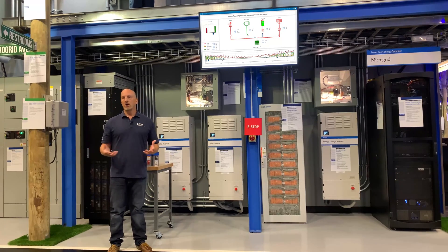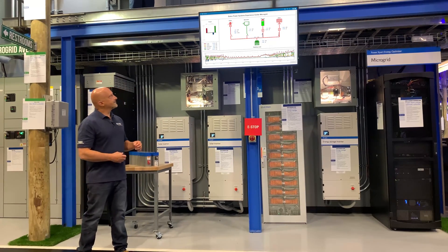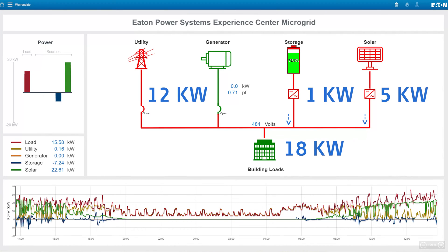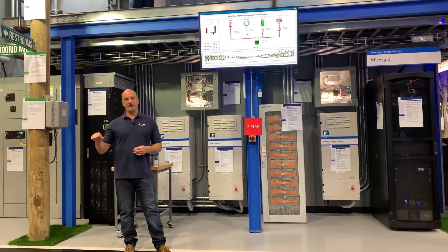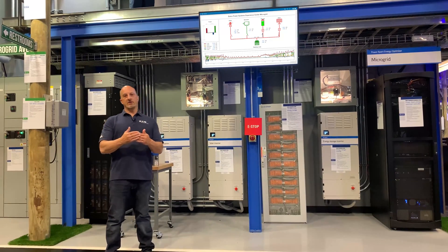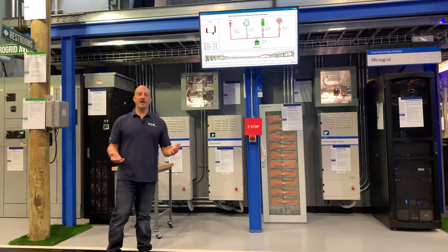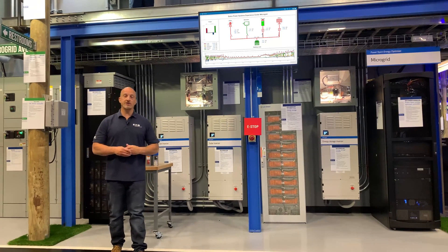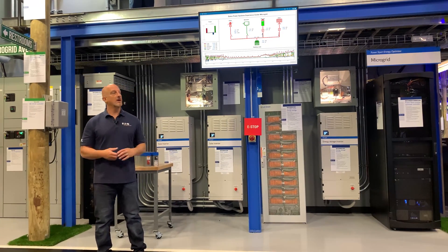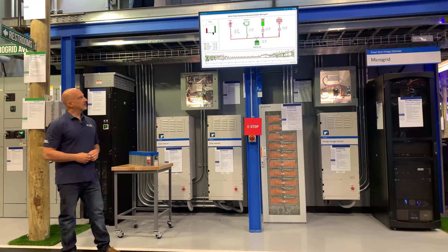Right now we have 18 kilowatts of power — 12 is coming from the utility and 5 is coming from the solar. We have certain states of charge we try to maintain on the batteries and certain requirements from the utility. From a load leveling standpoint, we can look like a nice flat line from the utility standpoint, which is great. We have targets like 10, 12, or 15 kilowatts to maintain so the utility sees a nice constant power.